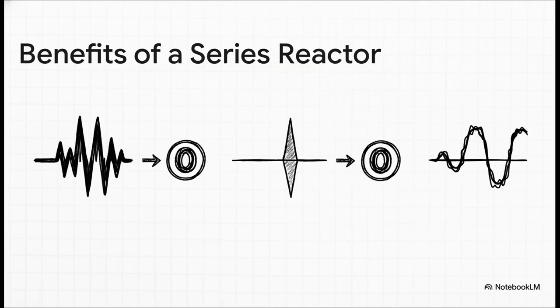And what it does is pretty incredible. The series reactor smooths out that wild inrush current, stops other voltage spikes, and even cleans up the electrical signal by getting rid of unwanted noise, called harmonic distortion. Basically, it tames the capacitor and makes the whole system safer and much more reliable.